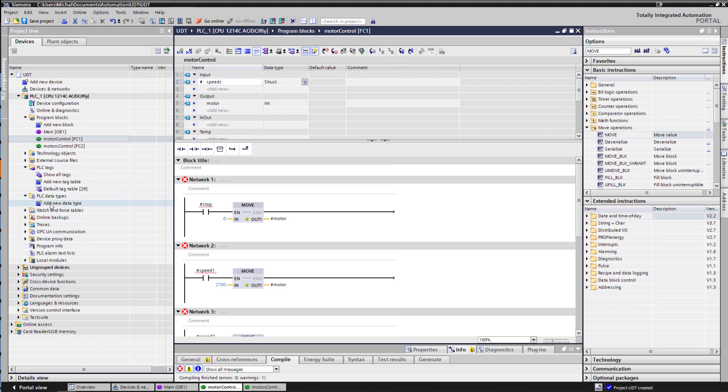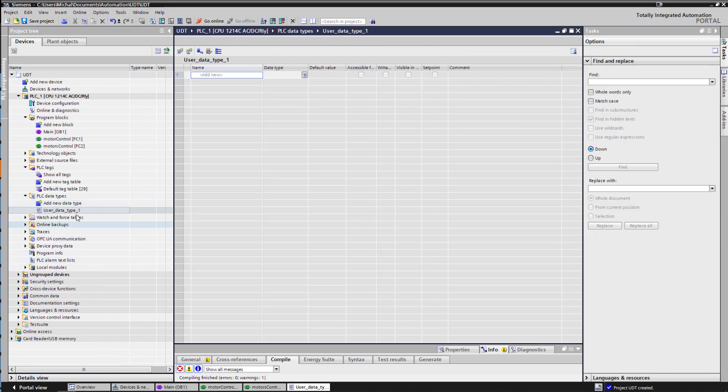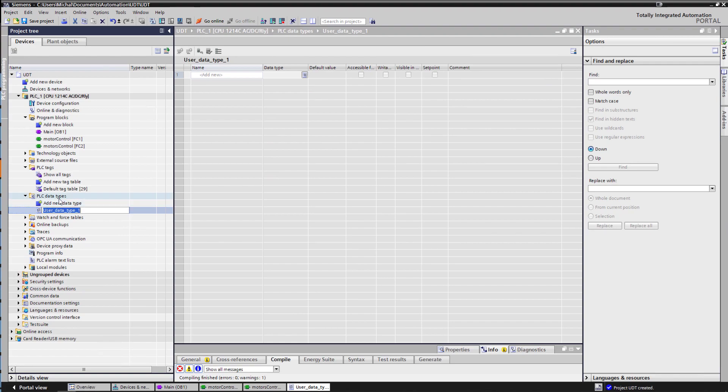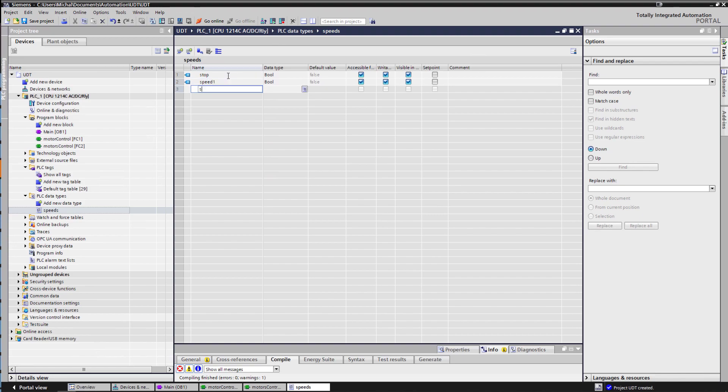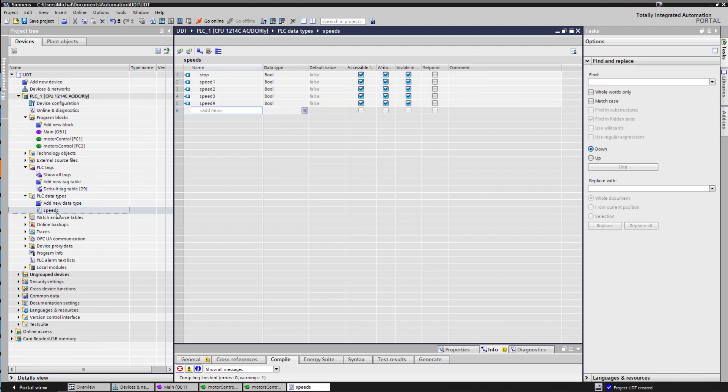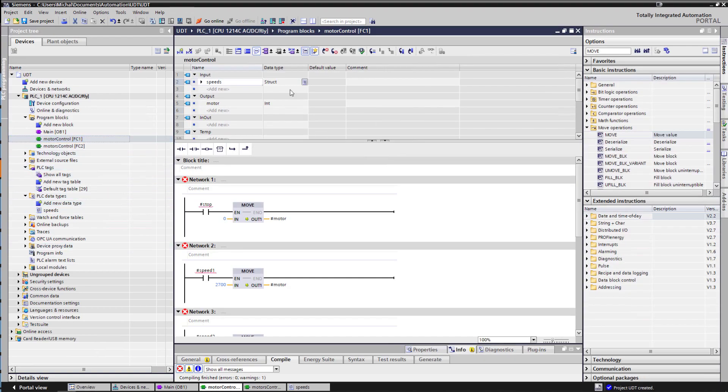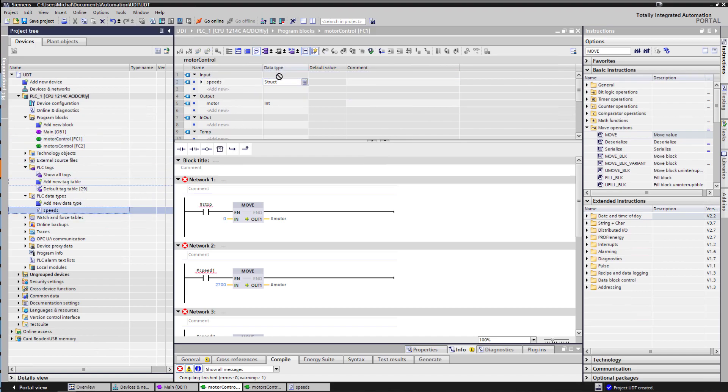So if we go and try a UDT rather than structure, we'd create ourselves a user-defined data type. We would call this one speeds. In here we would have stop speed 1, speed 2, speed 3, speed reverse and this can be used across your entire project. So this is like a function but for your tags. So as I said it could be across entire project. If we go to motor control, you could replace this speed with this guy.